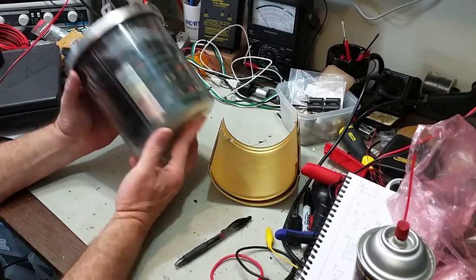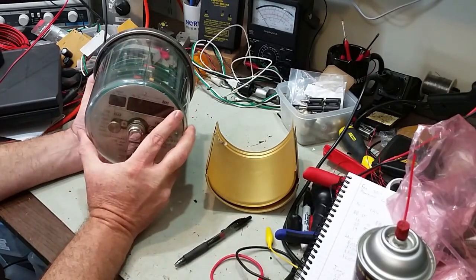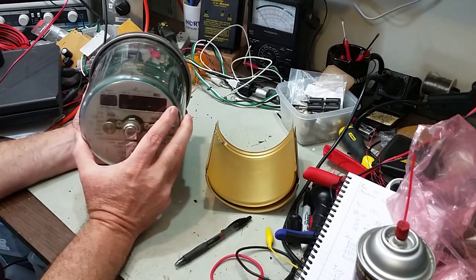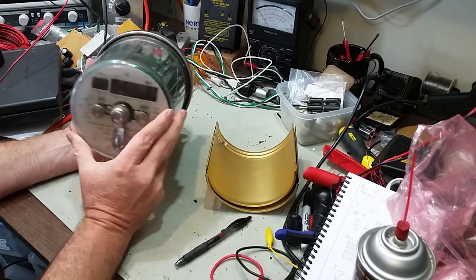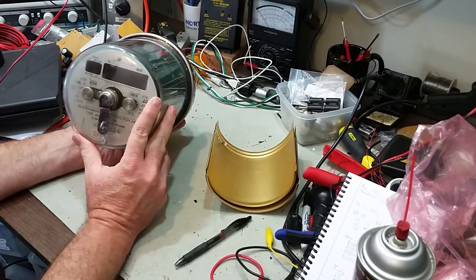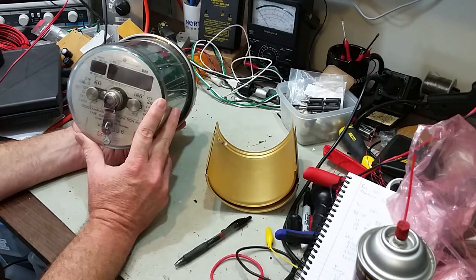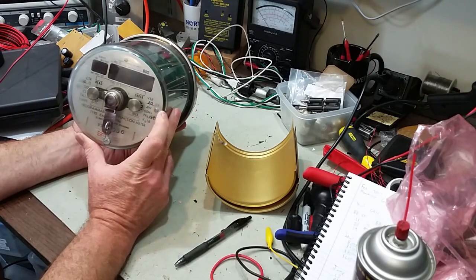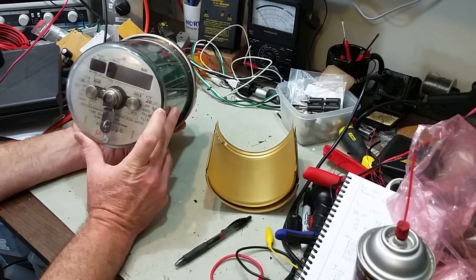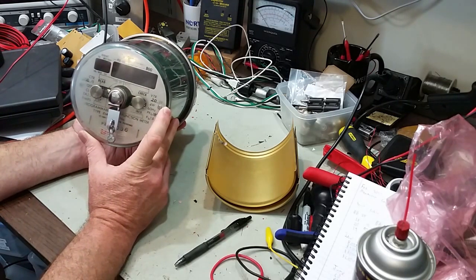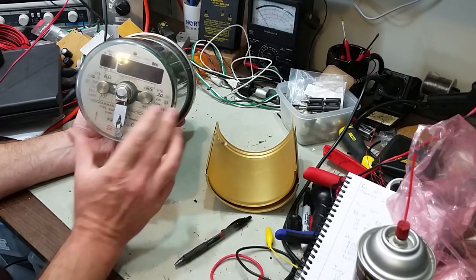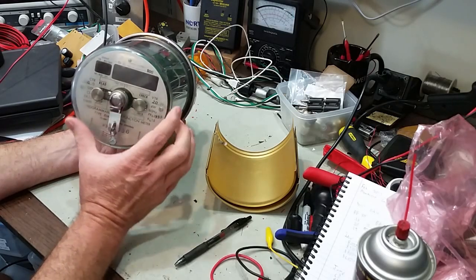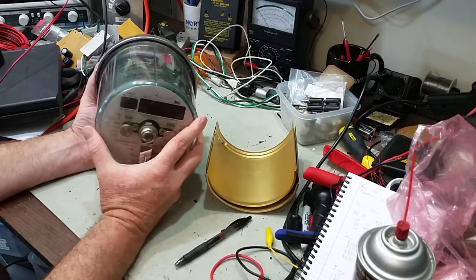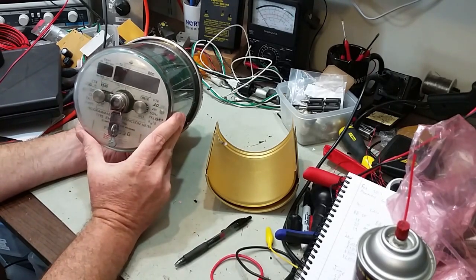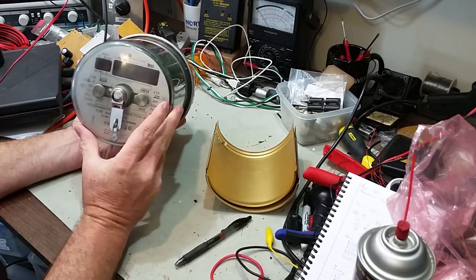It's called a transformer rated meter, unlike the meter on your house, which has no instrument transformer to step down voltage or current. Traditional electromechanical meters operated at voltages of maybe 13.8 kV, with much higher currents. So there are instrument transformers, both voltage and current transformers, that step it down to values normalized around 120 volts and 5 amps. Then you use correction multipliers to scale the values inside the meter so it gives an accurate reading accounting for those instrument transformers. Anyway, that's probably more than you ever wanted to know about metering.